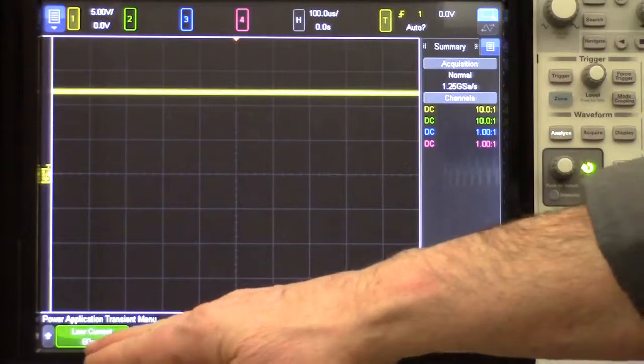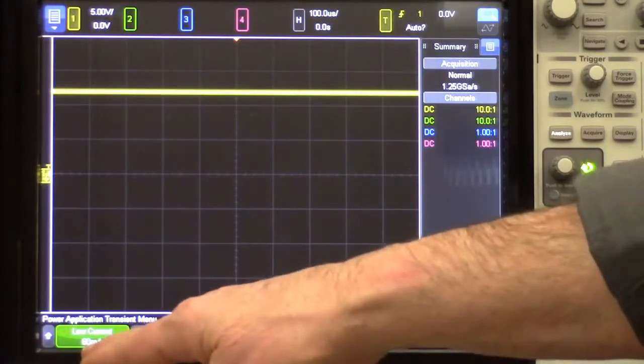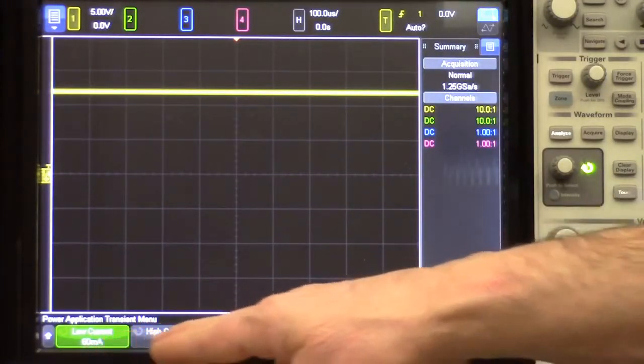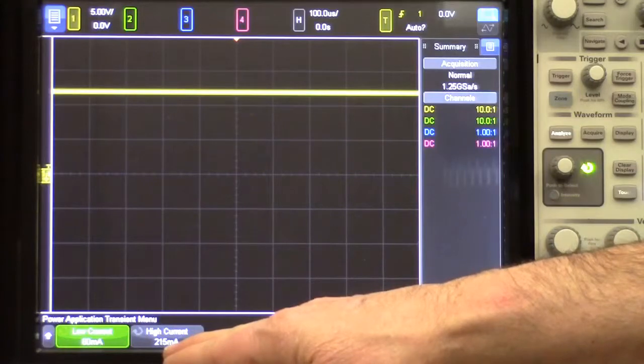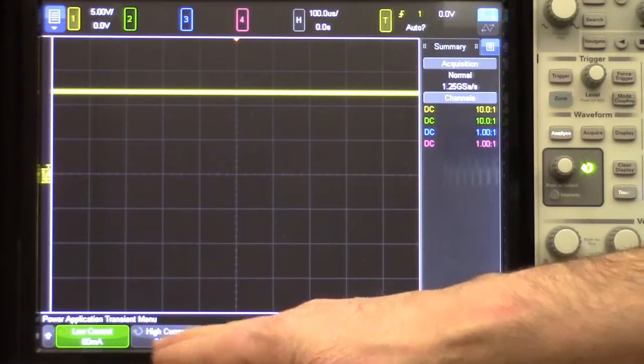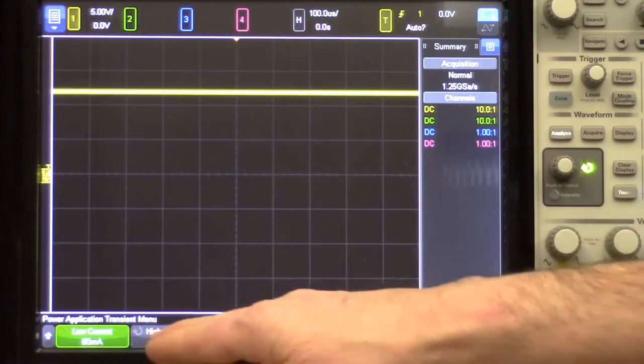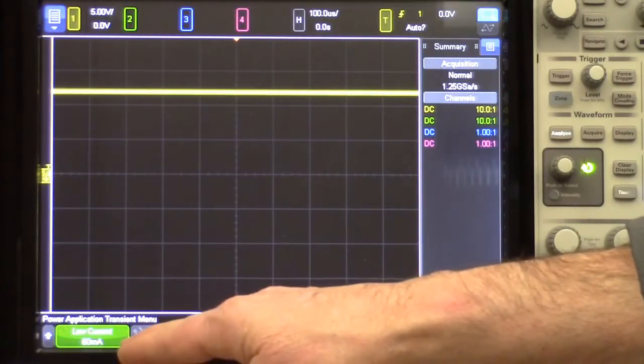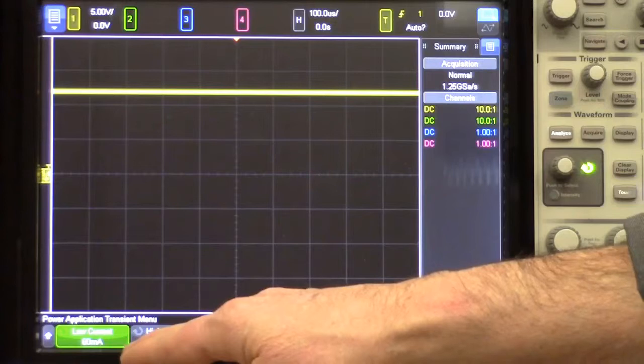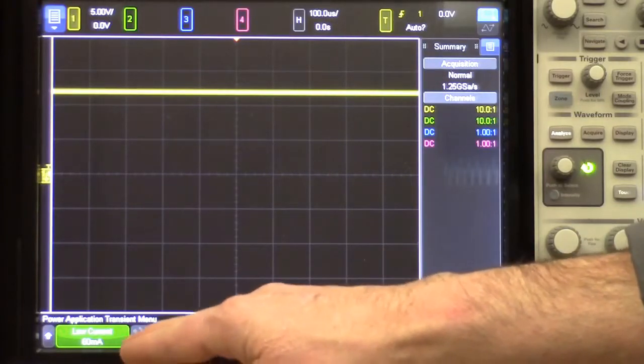We are going to alternate between a load that draws approximately 60 milliamps and a load that draws approximately 215 milliamps. Now, these settings are not that critical. The scope will use these values to set the trigger level on either edge so that it can trigger when it flips from one condition to the other. So it's going to set the trigger level in the mid-range of these two values.